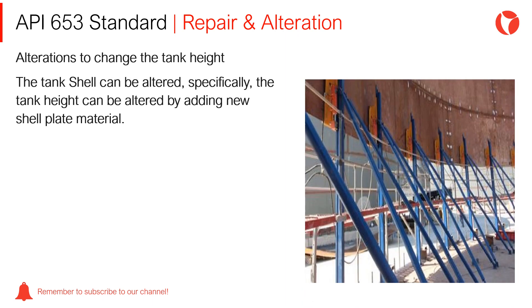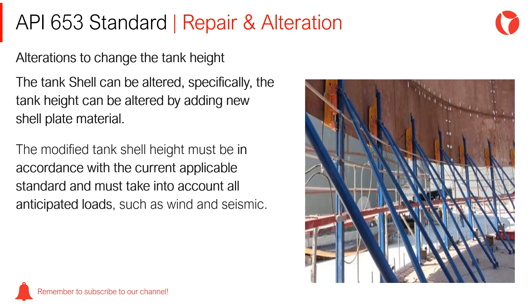The tank shell can be altered — specifically the tank height can be altered — by adding new shell plate material. The modified tank shell height must be in accordance with the current applicable standard and must take into account all anticipated loads, such as wind and seismic.